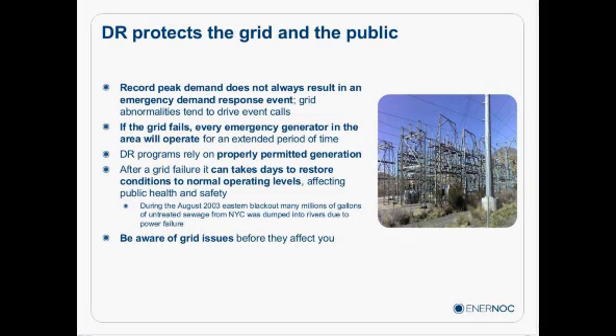So demand response protects the grid and the public. It's very important to note that record peak demand isn't always what drives a demand response event. Utilities procure enough power, they have enough infrastructure to satisfy their peak demand, even in a worst case scenario, in a situation where there's a long extended heat wave or a long extended cold snap. It's generally grid abnormalities that drive demand response event calls. A generator goes down unexpectedly. A transmission line goes down unexpectedly.